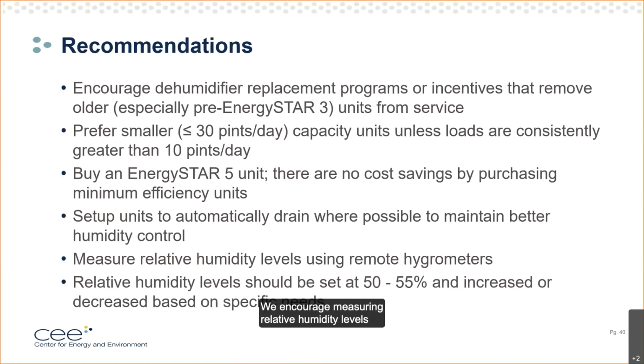We encourage measuring relative humidity levels with remote hygrometers. It's rare that people measure relative humidity in their homes; often the only reading they have is on the dehumidifier itself. But we found it helps to connect humidity levels in a basement with a reading they can view more frequently, say up by their thermostat, to connect their intuition of humidity with a measured value.